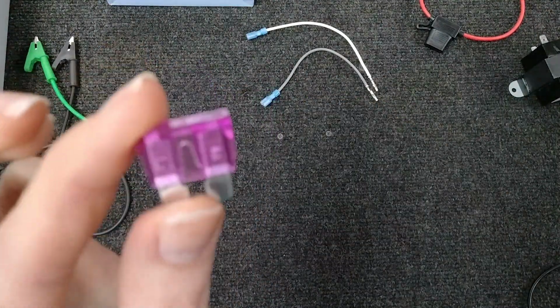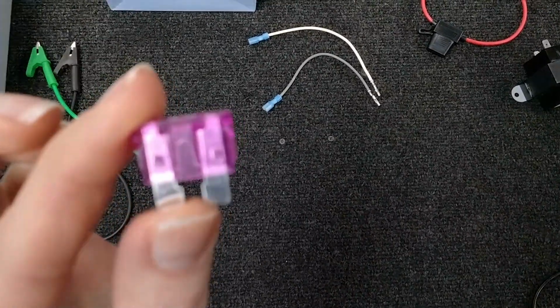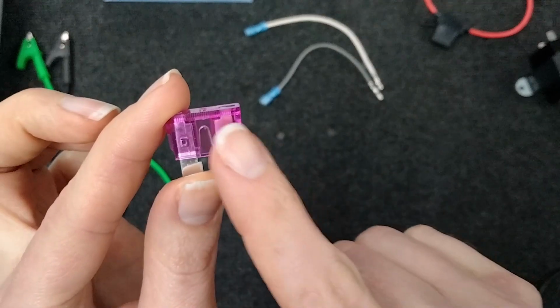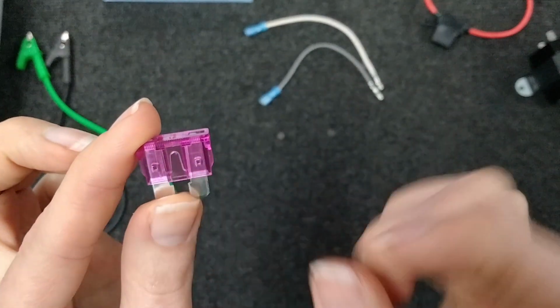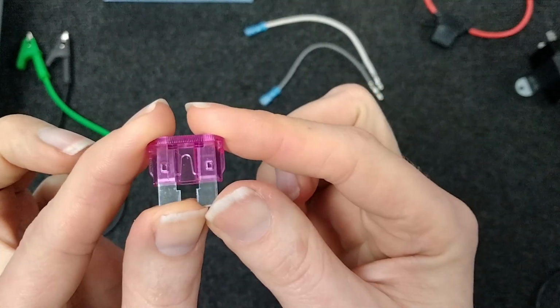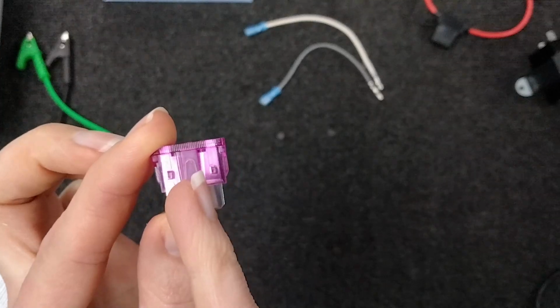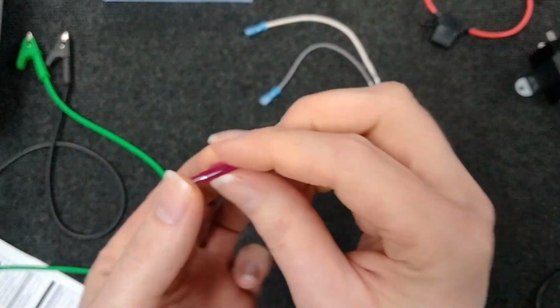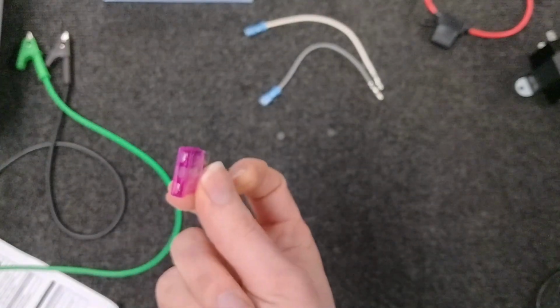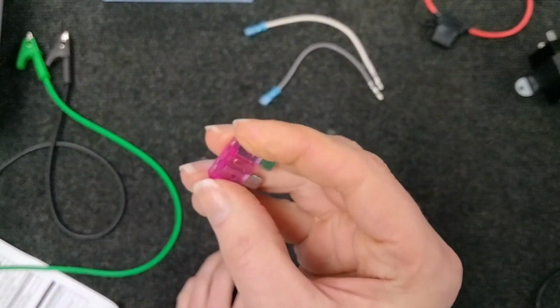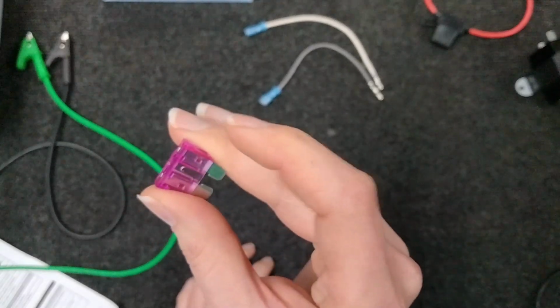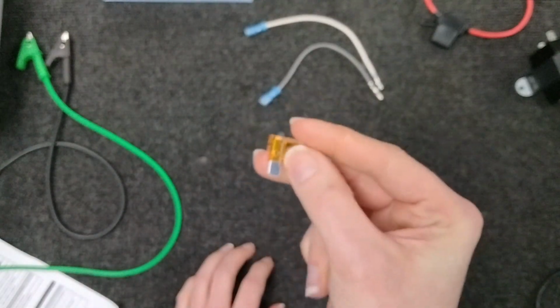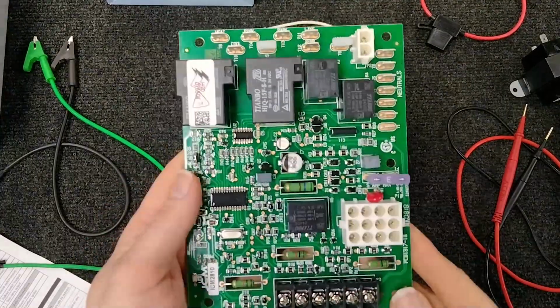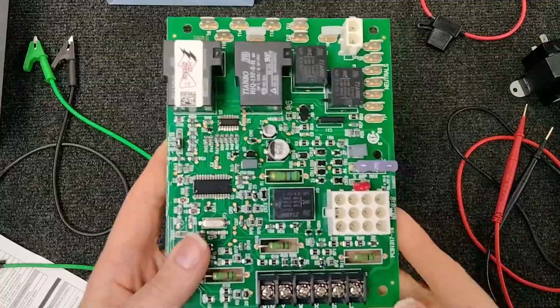Okay, now, so what are we looking for with these little guys? Well, as you can see, see if I can get this guy to focus on there a little bit better. There we go. As you can see, there's this little connection here. And that has to be solid. If there's a break or a small charring there, you know you've popped a fuse. And if you've popped your fuse, nothing will come on. So double check that your fuse is okay when you're going through to diagnose and make sure that your control board is not the culprit. And of course, checking your fuses to make sure that those are still good. Most of you are going to have single stage furnaces.